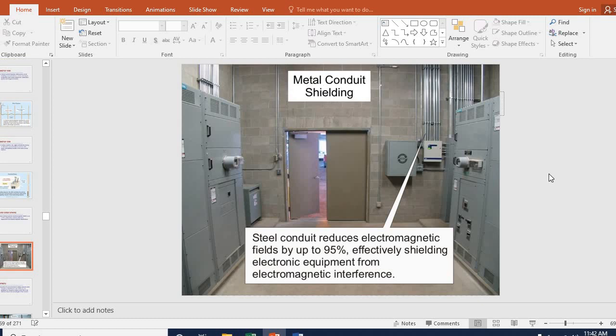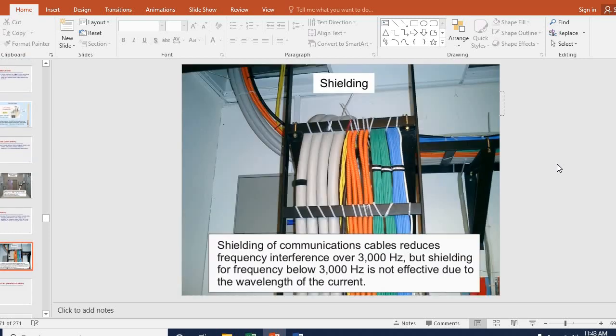Metal conduit, shielding. Most all your equipment rooms, you might see a little flex in there, but most of your conduits, steel conduit, and it reduces electromagnetic fields by up to 95%. That's a good thing. And just about all your motor control centers are run in conduit for that reason. If you've got a cable tray, a lot of communication, computers, cables, they'll still use shielding to help reduce the frequency interference.